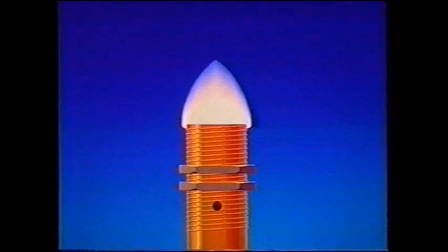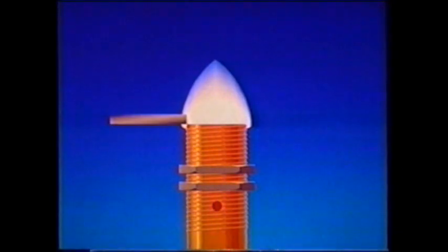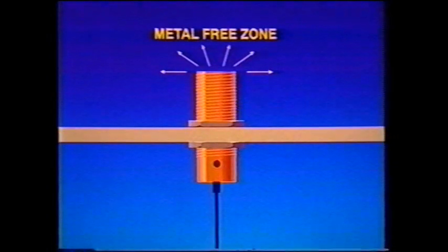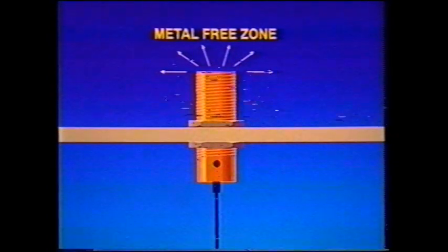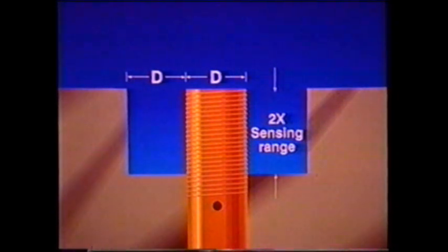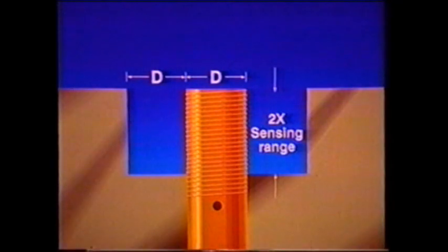The terms flush and non-flush refer to the mounting of the switch. A non-flush switch can detect a target which is not actually in front of the switch. The non-flush switch will also side-sense any bracket or other metal surrounding the tip of the switch. So non-flush switches must have a metal-free zone surrounding their active face. Cylindrical models must have a metal-free zone equal to the diameter of the switch surrounding the circumference. And there should be no metal behind the active face for a distance of twice the sensing range. For rectangular configurations, if there is metal on one side, it should be kept at a distance of 1.5 times the width of the active face.